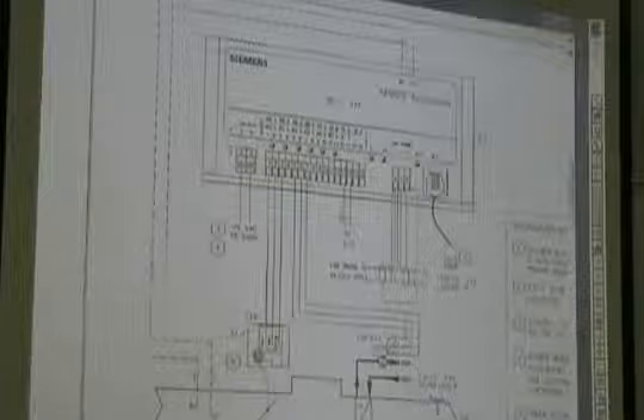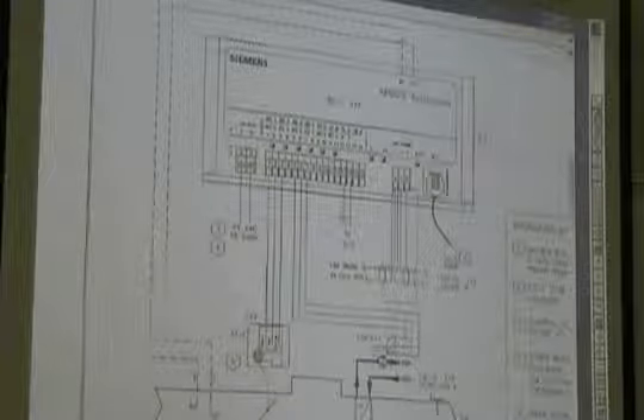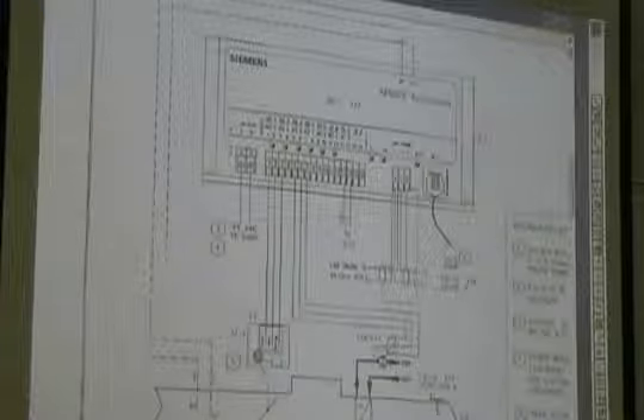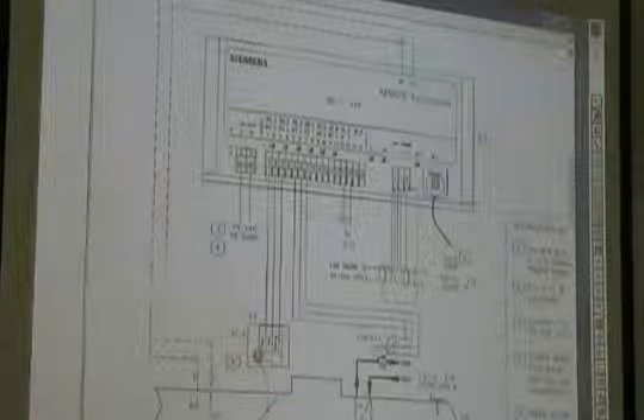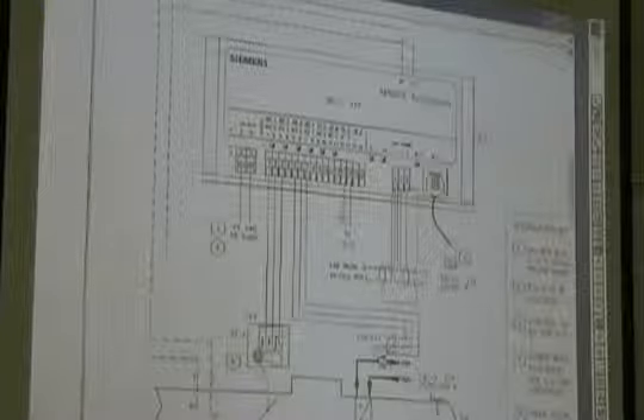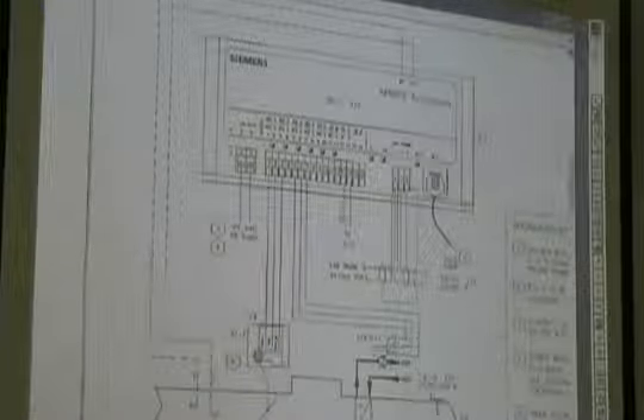And, go ahead. One I asked over at CFE, we had one box that I think everybody's worked on. The duct guy shoved the duct too far in there, and it pinched the tube inside there. You can't get it in there. They tried to move it out, done much different things. I don't see why we can't just add an aftermarket one a little further down the duct and call it done. Now, if the hoses are clogged, it won't read.